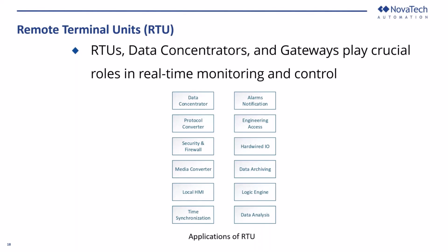Alarm notifications, that's important. You would probably get an alarm, or an SER from the relays that are sending that data saying this critical event happened. That gets pushed to the RTU, and you have the capability of alarming it, sending it to the crew there, or perhaps sending an email or text, whatever works for the clients usually. Some RTUs also have access to the relay or the meter via engineering access. So the RTU has the capability to tunnel into a relay or IED, allowing personnel to go to the RTU and access the end device for configuration, verification, and setting adjustments.